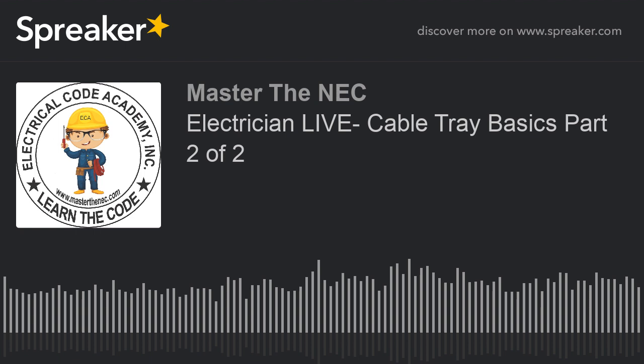Now let's go on to what's called single conductor cables, and we're talking about ampacity, and we'll talk a little bit about it. Okay? Now, here's what it says under 392.80(A)(2). And remember, when we're saying single conductor cables, we're also assuming that we're talking about single insulated conductors, and we're also assuming that we've got an industrial establishment, because that's the only place that single conductor cables or single insulated conductors can be installed in a cable tray. You with me? All right.